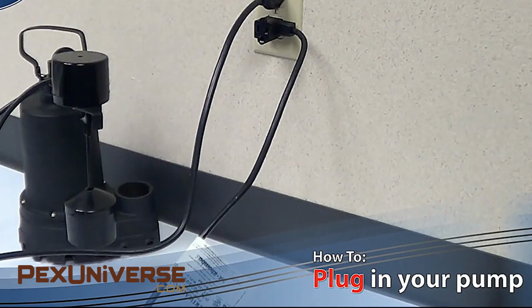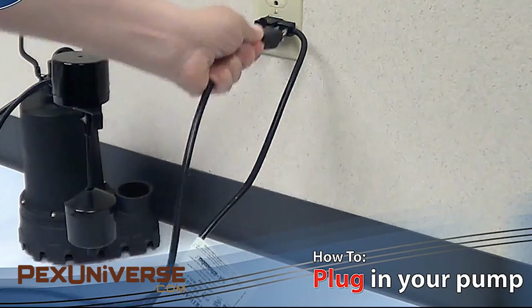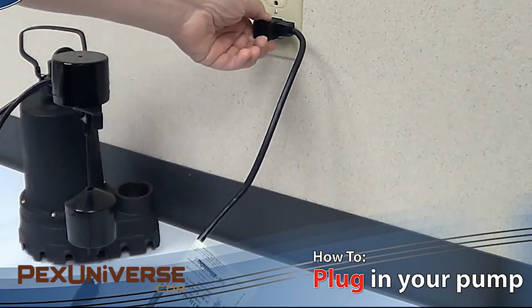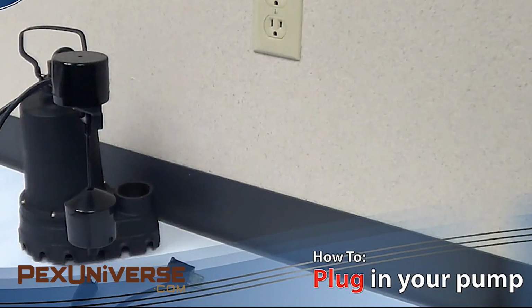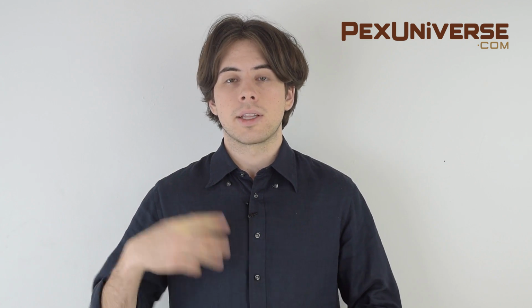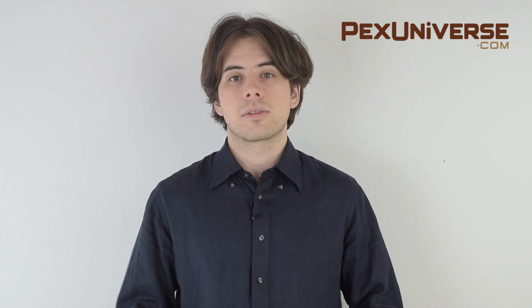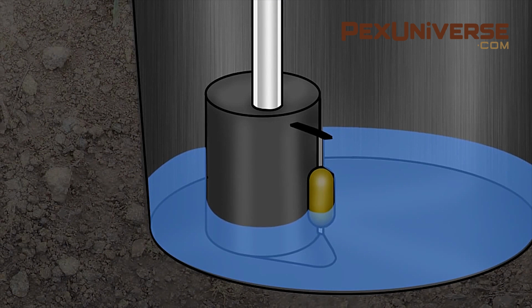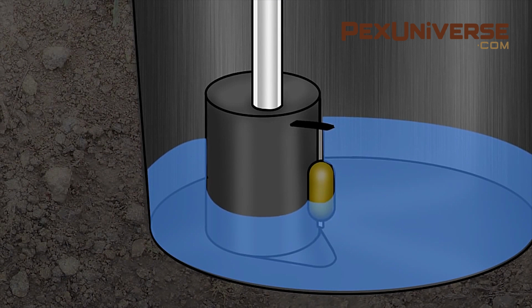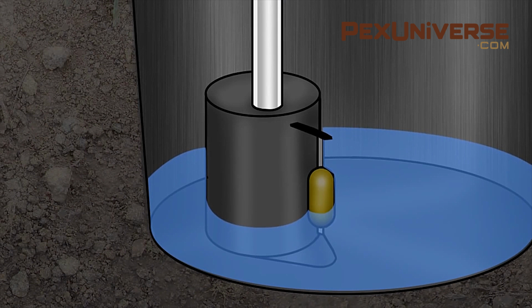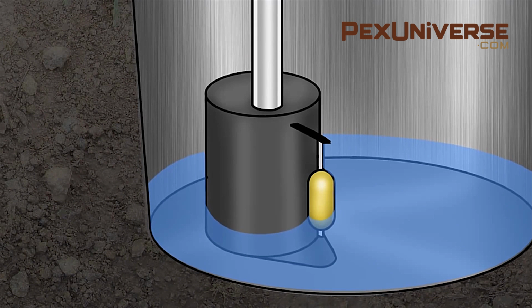The benefit of these is that you can unplug the cords from the wall, separate them, and plug the pump directly into the outlet without the switch, allowing you to test the pump by itself. The other switch options are regular switches, which come in variations, sometimes called integral, built-in, directly wired, tethered, electronic, or just vertical switches. A vertical mechanical float is a plastic or foam float that moves straight up on a rod as water enters to activate the pump. When the float goes to the bottom, it pulls the rod down to turn off the pump.